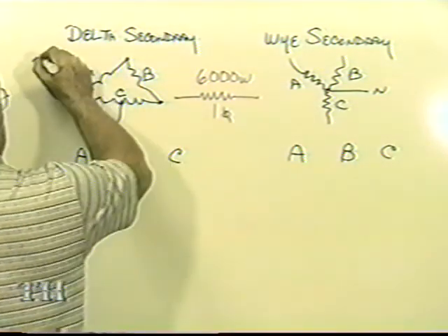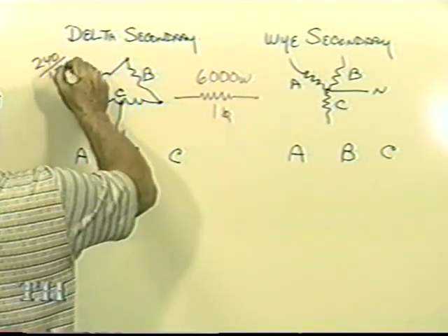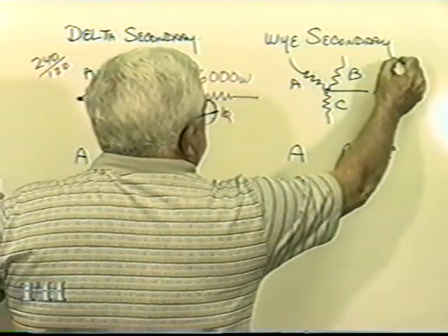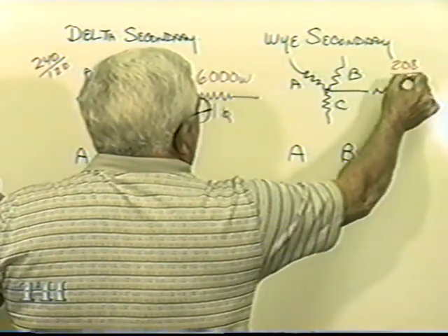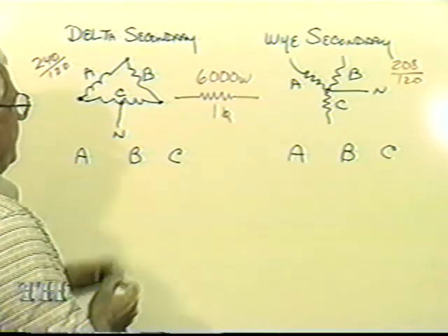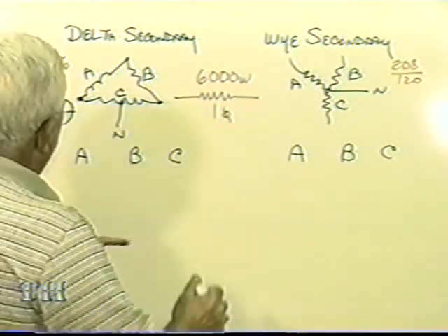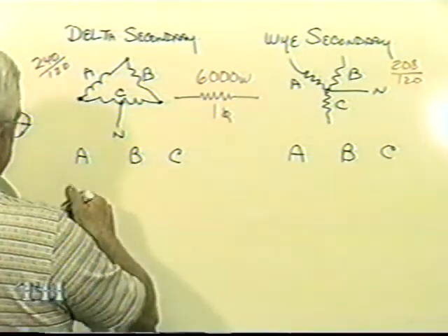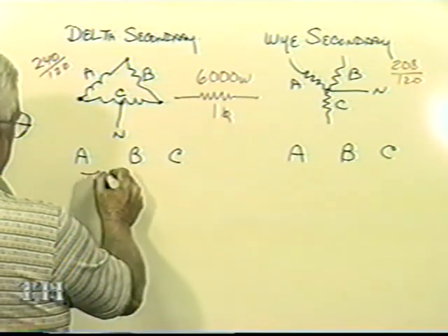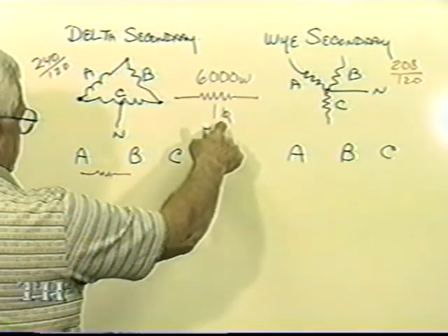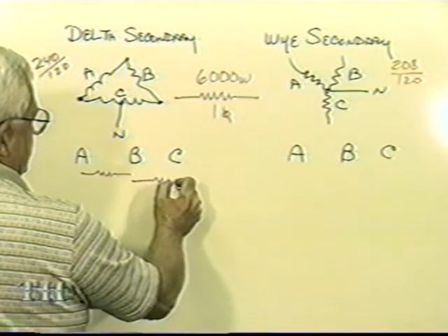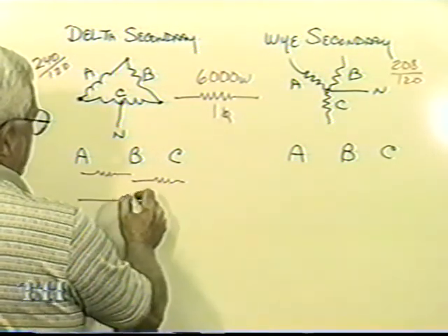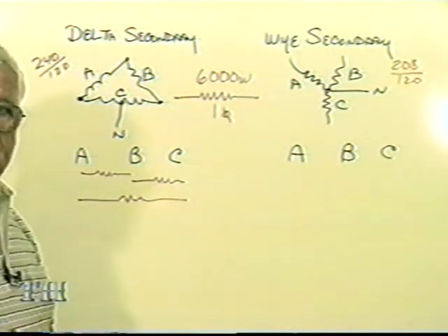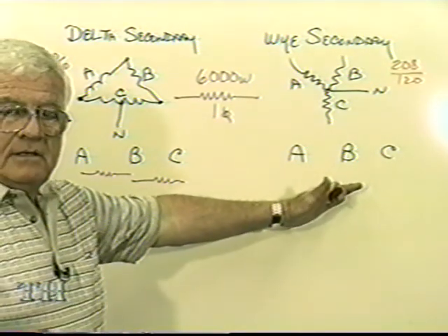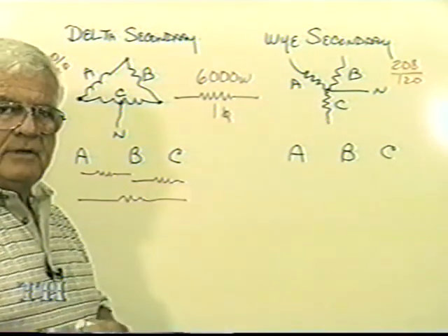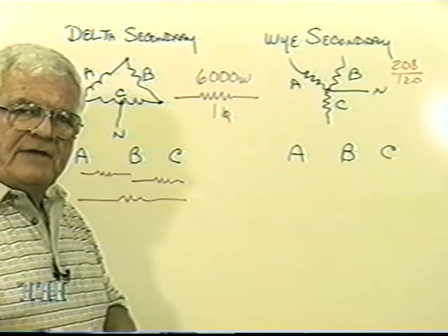We'll say this is 240, 120, and this guy's 208, 120. Well, for me to hook this up, I would have to connect that 6,000 from A to B, single phase, or I could go from B to C, or from A to C. Same way over here, to connect it in the panel board. But here's what you want to see when you have to balance loads.